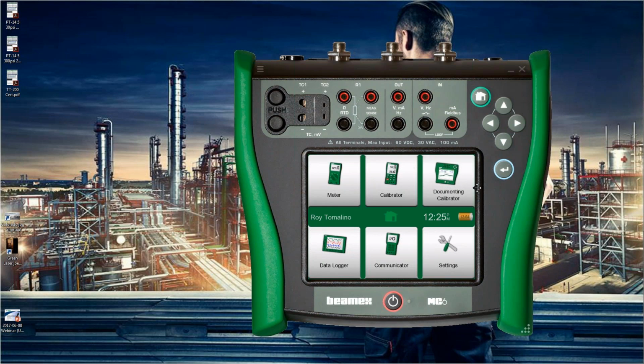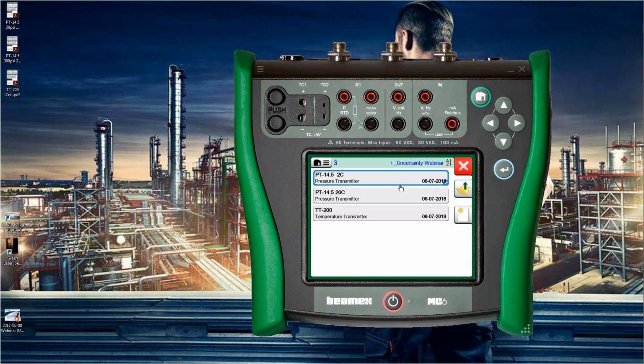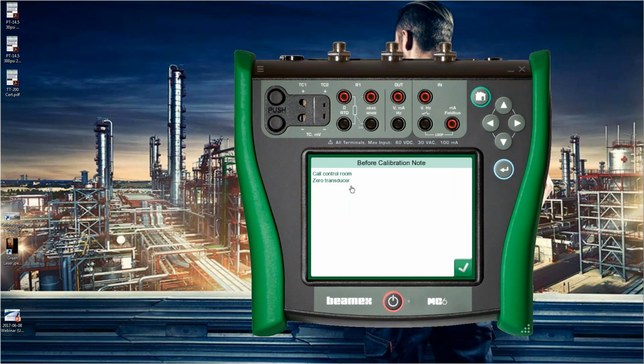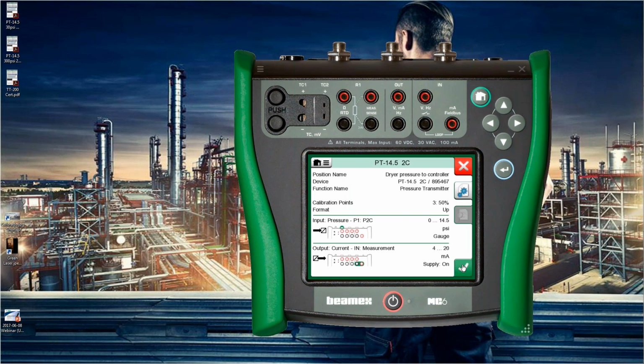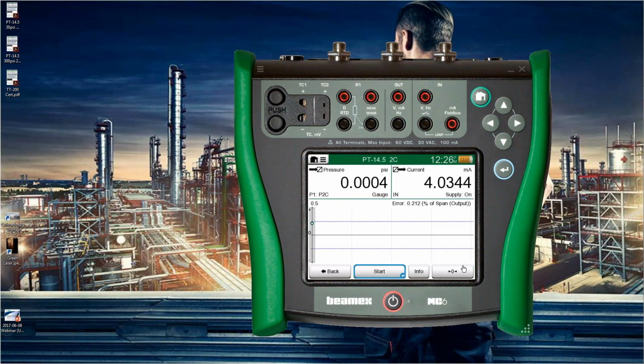So I've already taken the time to load these onto the calibrator, and the top two are what I'll do. So I have it called PT-14.5, and that's because the range is actually 14.5 PSI. I've got all my connections, hopefully. And there was a note flashed up right away that said, make sure to zero my pressure transducer. That's what I'll do right now. I'll hit the zero button. And now I'll hit start.